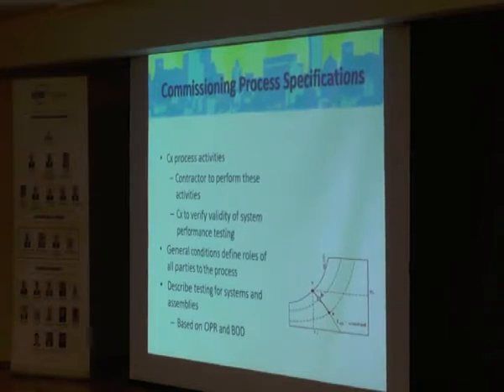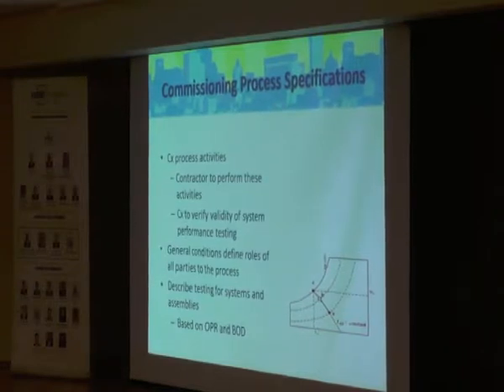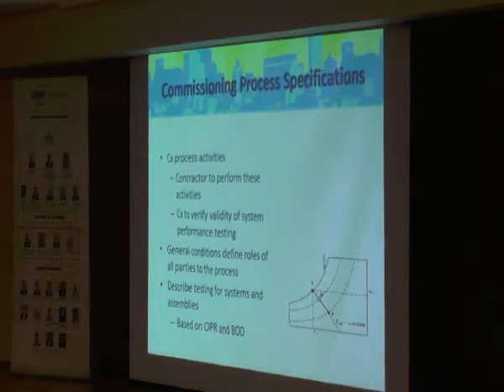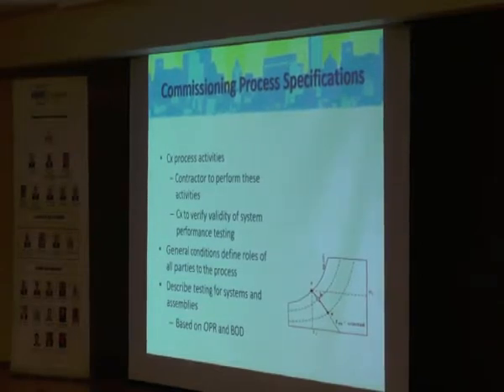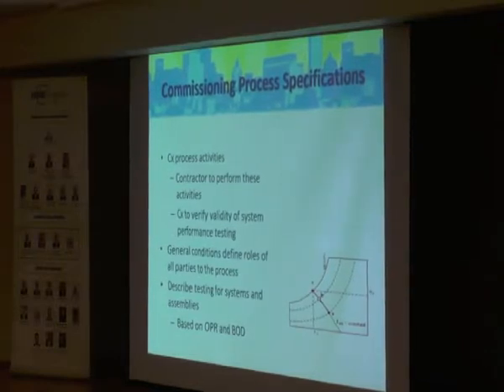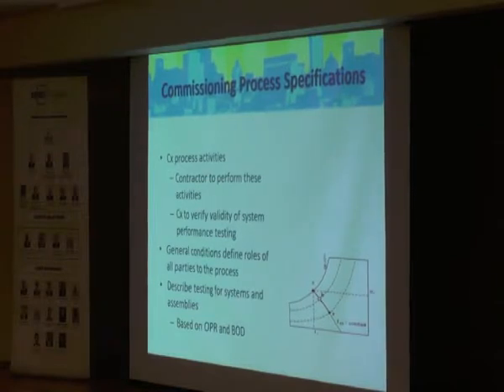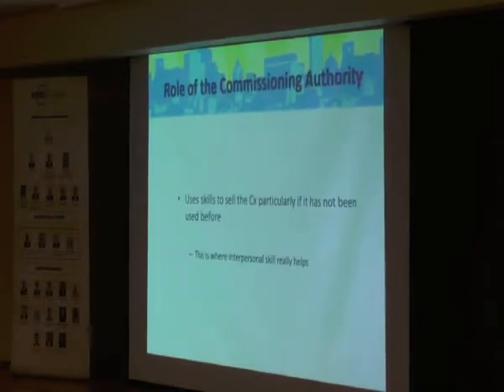The commissioning specification covers the commissioning process activities the contractor performs during construction. The commissioning authority verifies the validity of systems performance testing, defines the roles of all parties, and describes testing for systems and assemblies based on the OPR and basis of design. These specifications become part of the project specification so they can be priced into the contract.